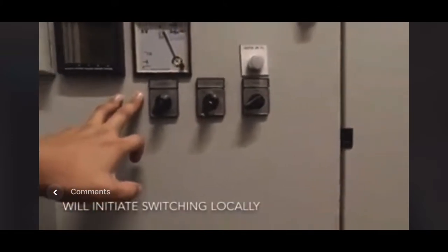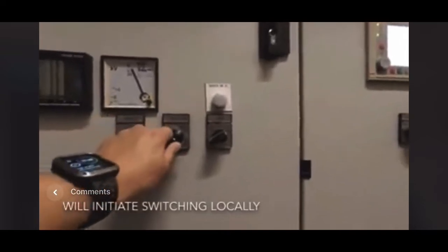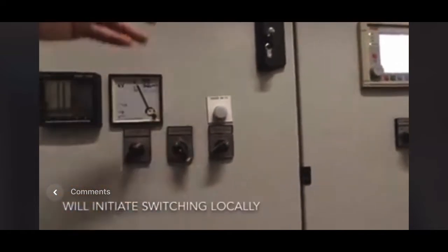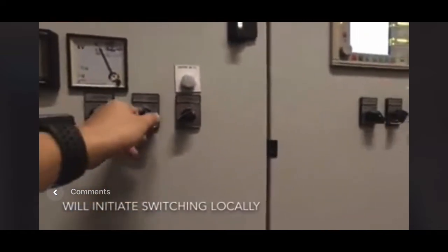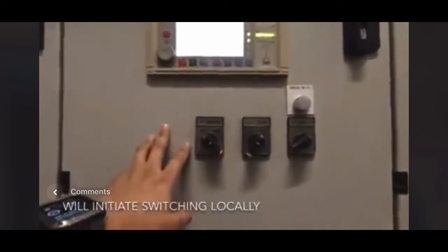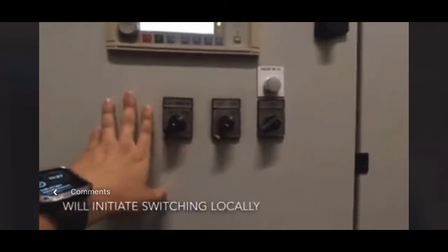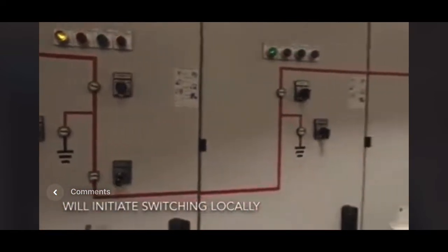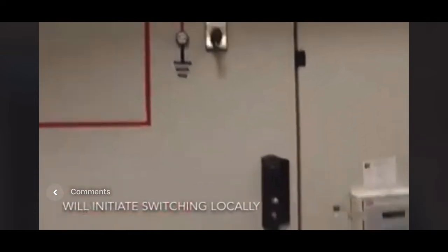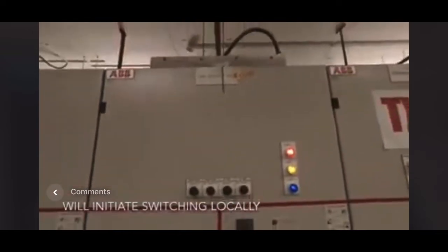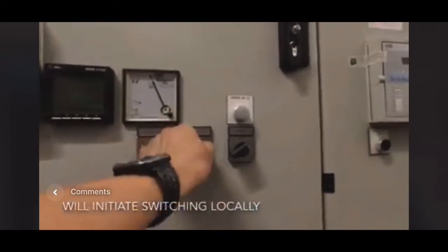Before we do any switching, make sure it goes from remote to local first if you are going to use manual mode. Otherwise, just use remote mode. If you want to do the coupling, then switch from auto to manual, from remote to local, because we are going to do it under manual mode. And then here also from remote to local. And Incomer number 1, remote to local.